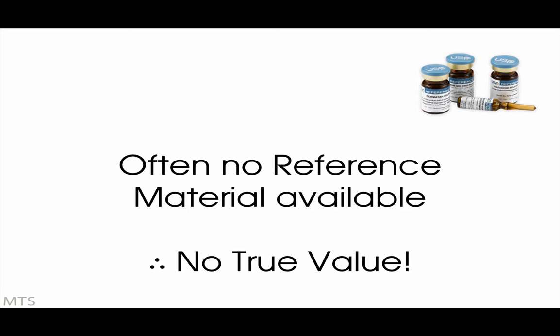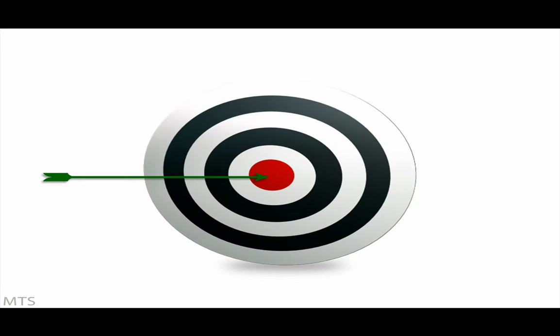The purpose of the accuracy investigation is to show that the value determined by the test is close to the true value, shown here as how close the arrow is to the centre of the target. If you don't know the true value, then you can't assert that the test method is accurate.